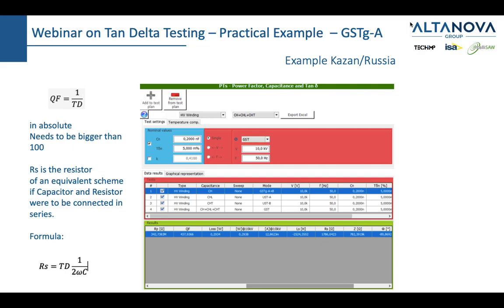So one user is saying IEEE C57.161-2018, dielectric frequency response. This is an answer, but it is for a sweep for tan delta, yes, this is a norm for tan delta at very, very low values of frequency. And with this method, you're actually testing the paper, the cellulose, which usually, as we said, contains most of the water.